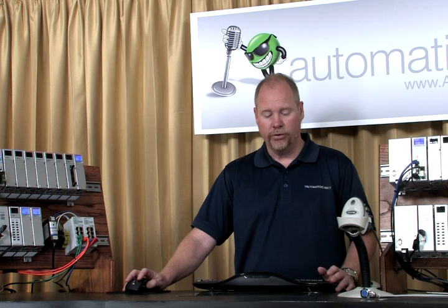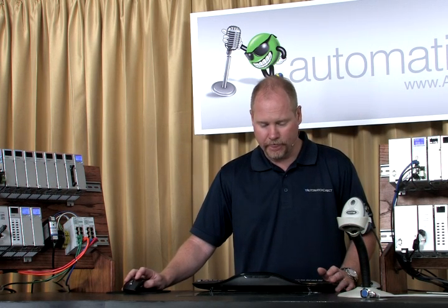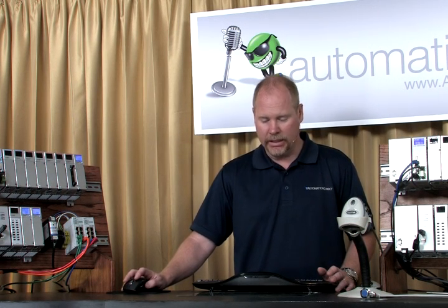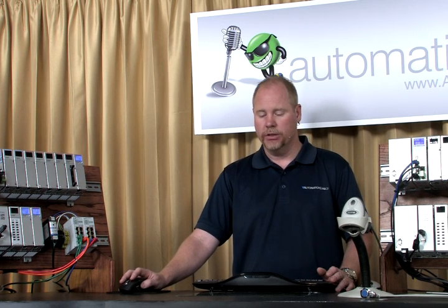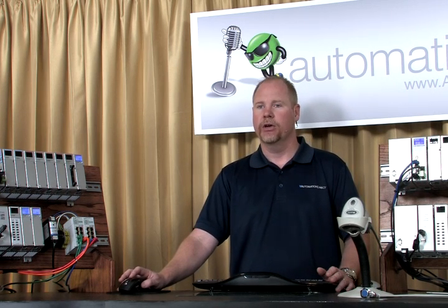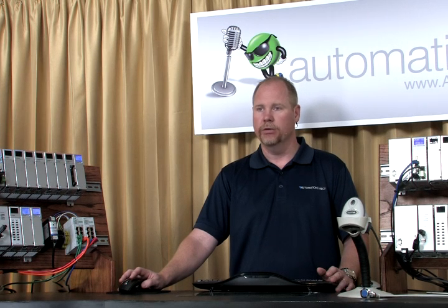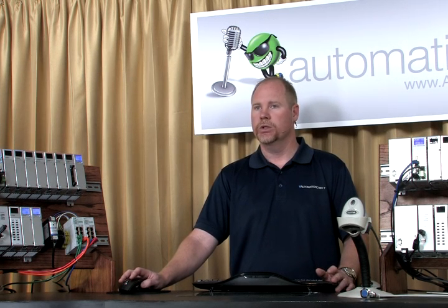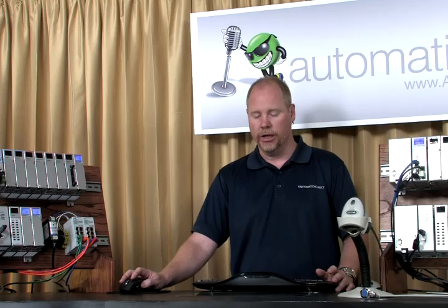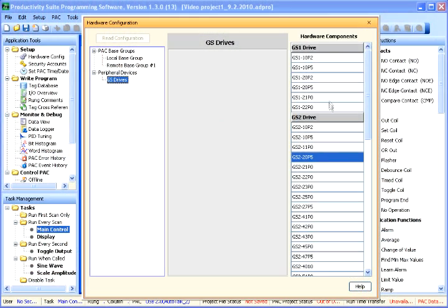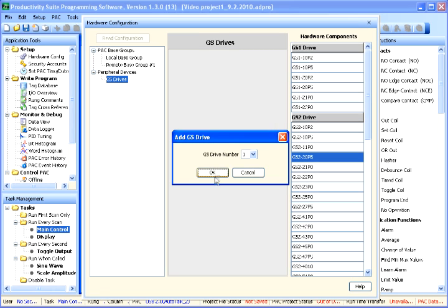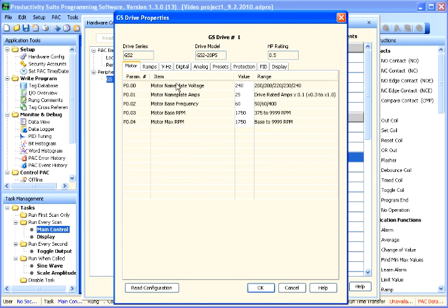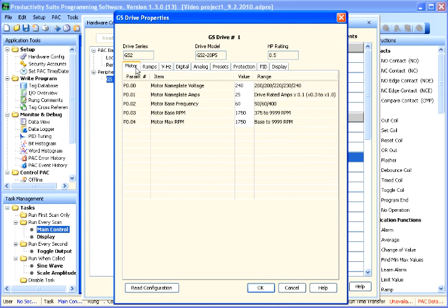And then we also have peripheral devices. In the peripheral devices, we can add GS drives. The GS drives and the DuraPulse drives are available to be connected to the remote I.O. network when using the Ethernet adapter, the GS-EDRV. So if you take a drive and drop it into your GS drives configuration, it'll automatically ask for the drive number. You can say OK, and then it gives you all of the parameter options for the GS drive. This configuration is now stored within the PAC project, and you have the option of transferring this configuration to the drives every time you power up the system.